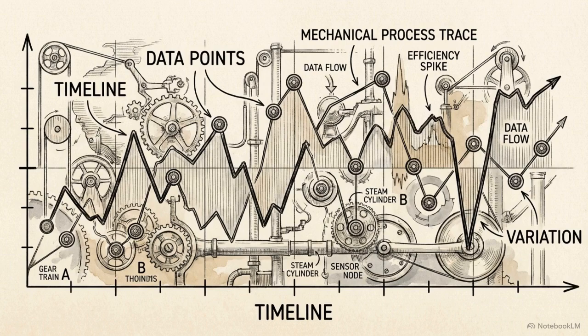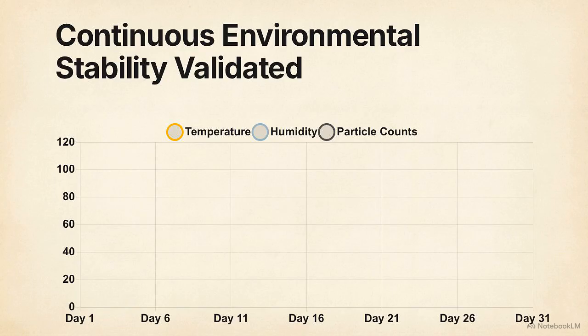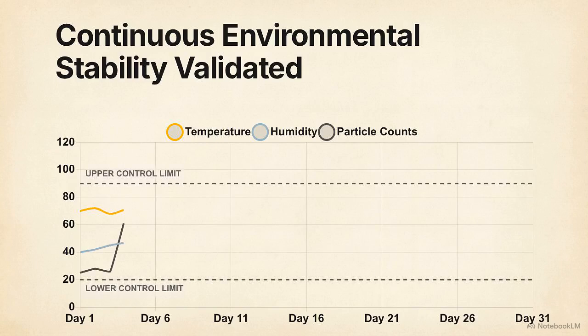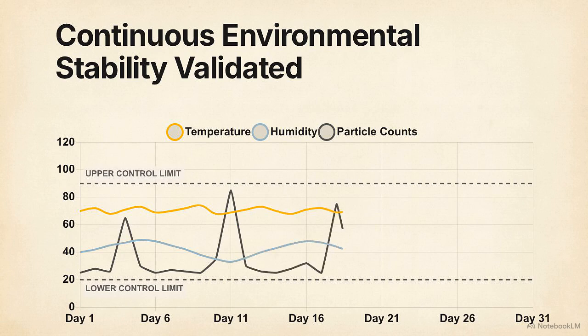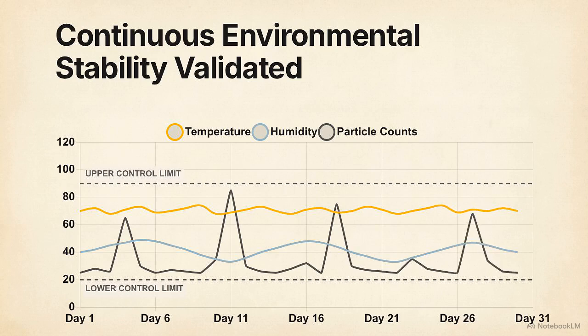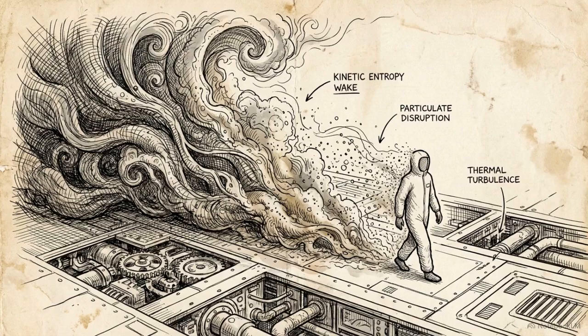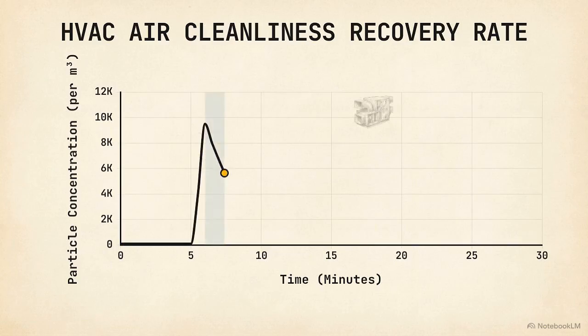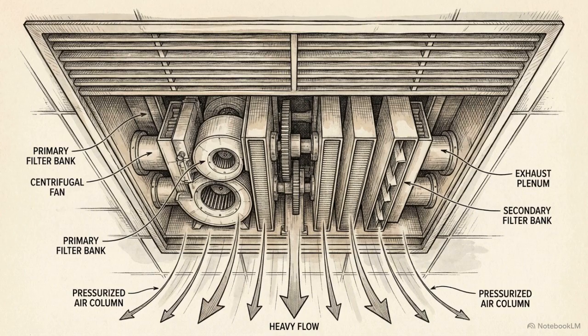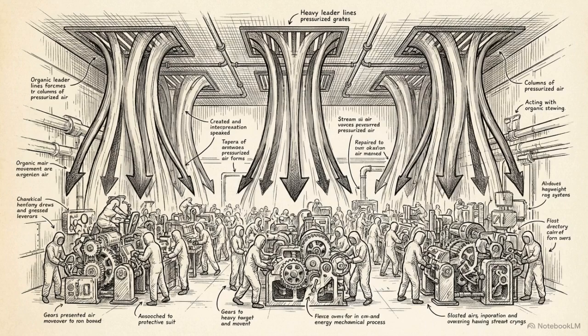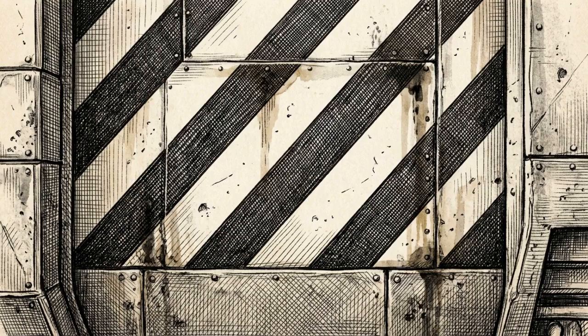The first PQ strategy is extended monitoring. This chart shows the transition from single-point testing to continuous, relentless data logging over an extended time frame. Over several days or weeks, sensors track temperature spikes, humidity fluctuations, and airborne particulate concentrations. Human movement directly spikes particulate generation in the room. This tests the HVAC system's ability to clear the air rapidly and return the suite to baseline cleanliness. PQ extended monitoring evaluates the system's real-time endurance, proving it can actively scrub the environment faster than humans and machines can pollute it.